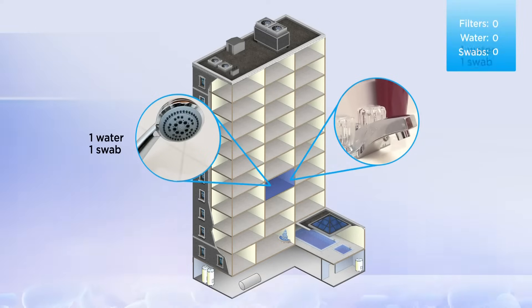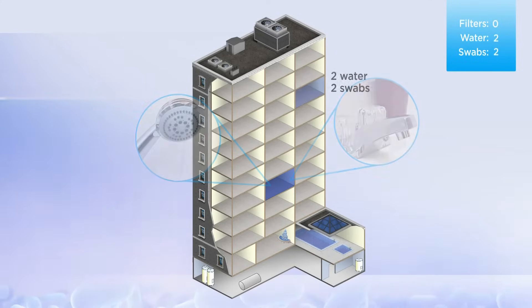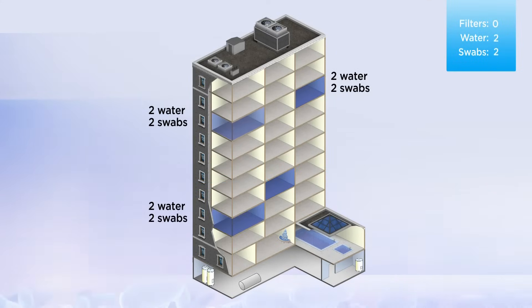Because Legionella do not grow in cold water below 77 degrees Fahrenheit, it is generally not necessary to collect cold water from the premise plumbing for culture.